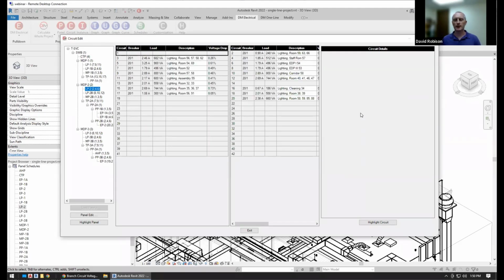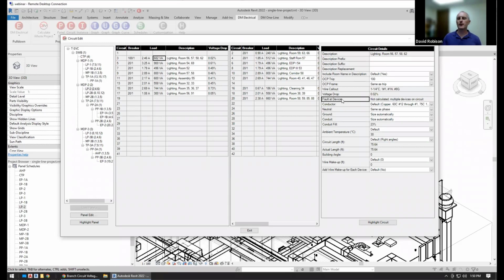So if I come back here, if we go to a larger size breaker, it becomes more clear. If we go to a 100-amp breaker, we're just going to use a number 8 ground, which is the standard equipment ground for a 100-amp breaker. The assumption being that our conductors are being sized to match our breaker, and so that we don't trigger the NEC requirement to upsize the ground proportionally.